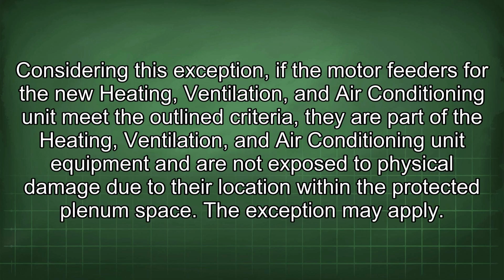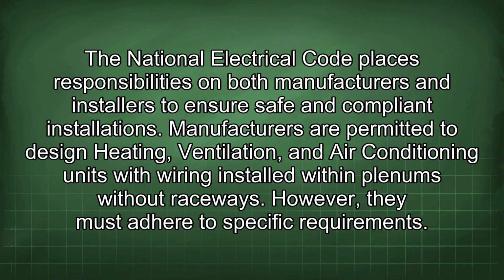Considering this exception, if the motor feeders for the new heating, ventilation, and air conditioning unit meet the outlined criteria, they are part of the heating, ventilation, and air conditioning unit equipment and are not exposed to physical damage due to their location within the protected plenum space. The exception may apply. The National Electrical Code places responsibilities on both manufacturers and installers to ensure safe and compliant installations. Manufacturers are permitted to design heating, ventilation, and air conditioning units with wiring installed within plenums without raceways. However, they must adhere to specific requirements.